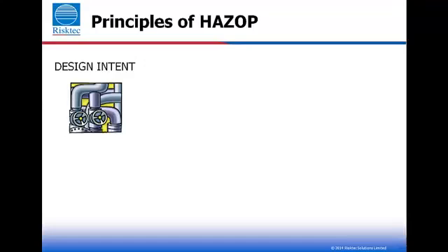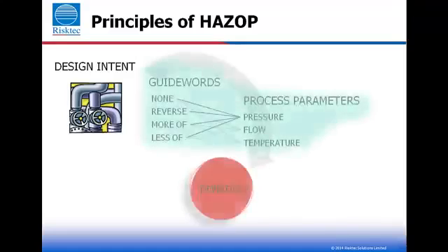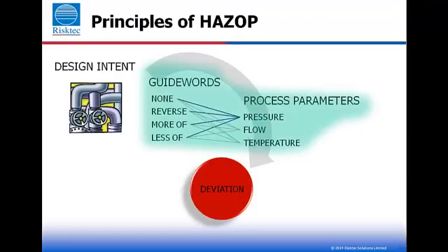The main thought processes that need to be established are: What is the intention of the node? What do we expect to happen in this particular piece of equipment, or at this stage in the operation? What possible deviations from design intent may occur? What can go wrong? We do this by taking a series of guide words, applying them to parameters, to produce the deviations, such as no flow, high pressure, low temperature.